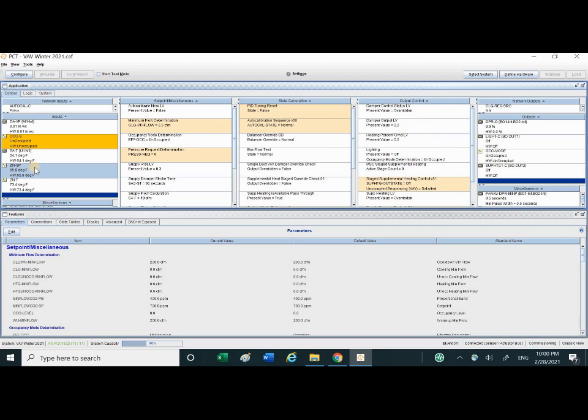Thermostat, the set point now is 65.8 degrees Fahrenheit. And this is the zone temperature, which the thermostat senses now. And on the output side, this is the damper position. Now it is zero, because the set point is lower than the zone temperature, so the damper position is closed. Here it's closed.